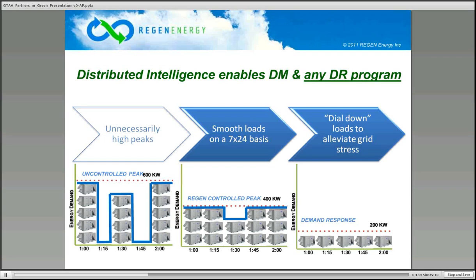This year we're using 15-minute segments; next year it'll be 10-minute segments. So we dial it down by 1 or 2 notches, and that gets you the demand response reduction you need without creating a huge wall of heat and humidity that you'd get if you simply turned everything off for a little while. You don't have to pick which areas are going to be starved, because everybody participates in this. So it's a much more intelligent approach to demand response.